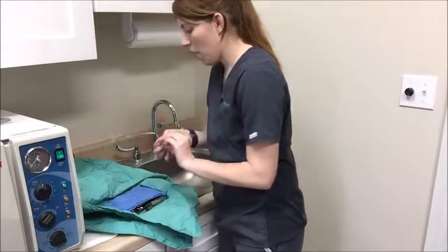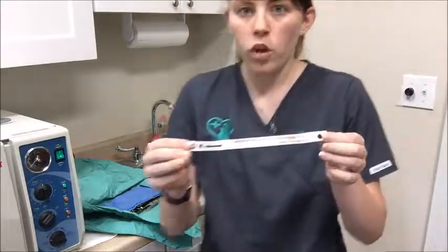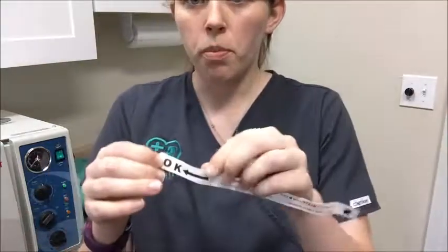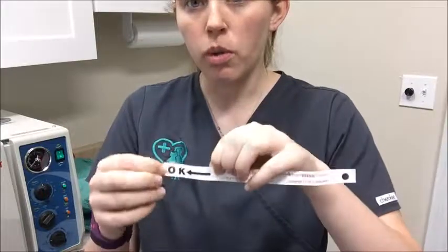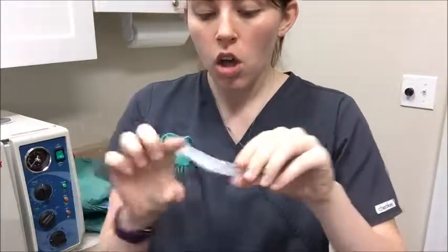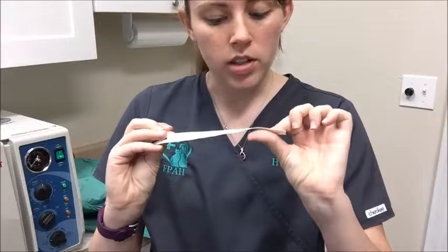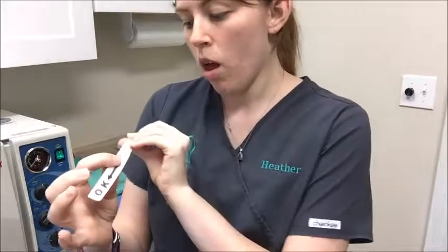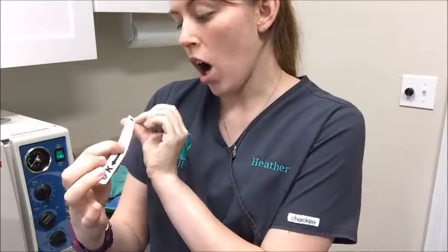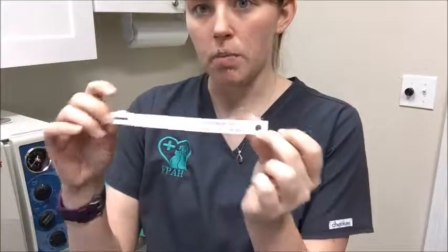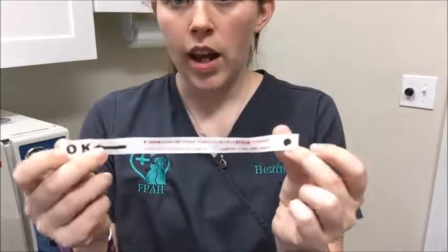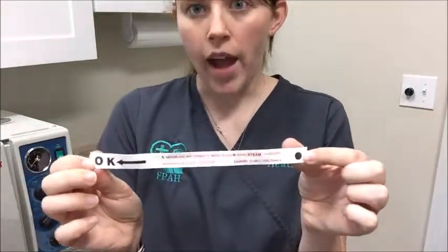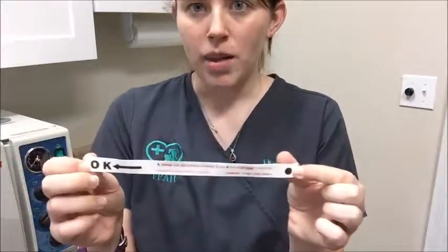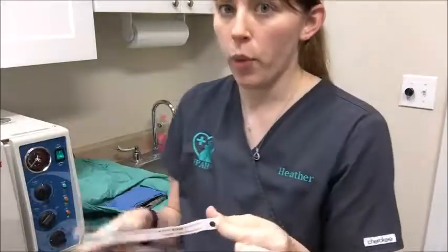Alright, and right on top is my indicator strip, which the OK has turned black. It wasn't visible before going through the autoclave, so this whole strip and this other circle turned black as well. It says OK, arrow, and dot change to mark black when steam processed. So the OK, the arrow, and the dot have all changed black, meaning that my pack has been exposed to the appropriate amount of steam all the way through.